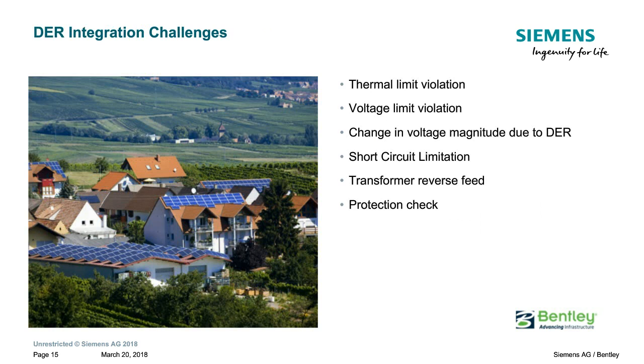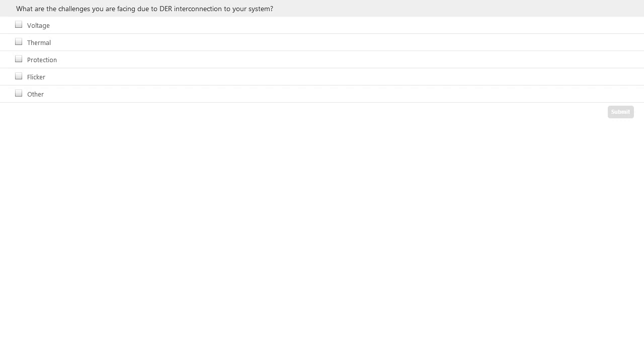Distributed energy resources provide many advantages; however, integration presents significant challenges. These include thermal limit violation, voltage limit violation, rapid voltage fluctuation of PV causing flickering issues, short circuit limitations, transformer reverse feed, and protection coordination issues. A poll question: what are the challenges you are facing due to DER interconnection to your system? You can choose multiple options: voltage, thermal, protection, flickering, and other issues.